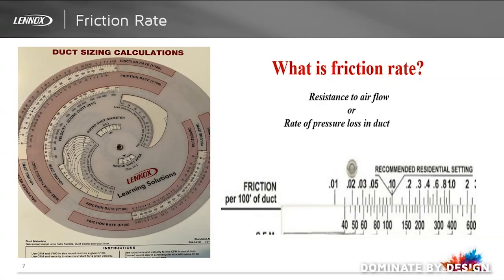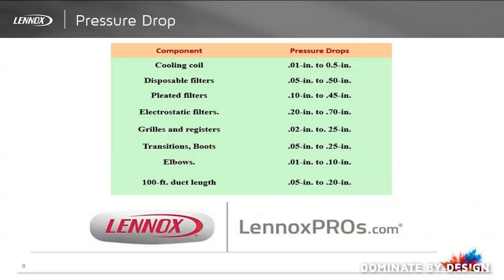Now we're going to look at friction rate. Friction rate is the resistance to airflow, or rate of pressure loss, in a duct system. It is important to know that all devices installed in a duct system external to the equipment have a pressure drop — cooling coils, pleated filters, grills and registers, as well as each 100-foot section of duct work.